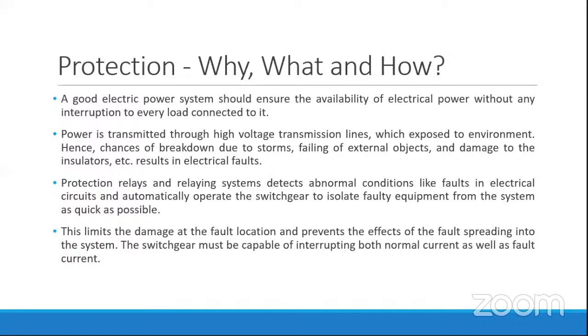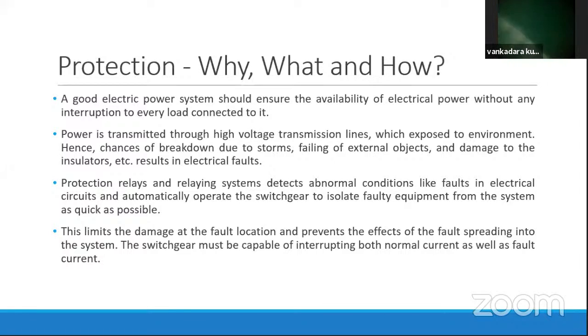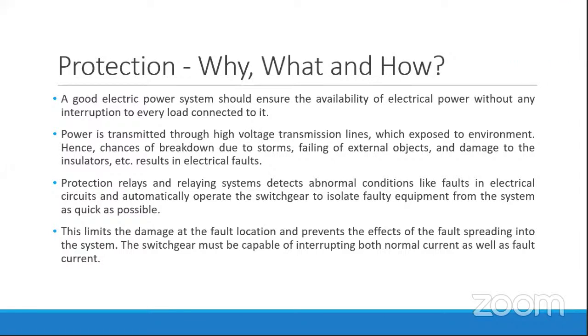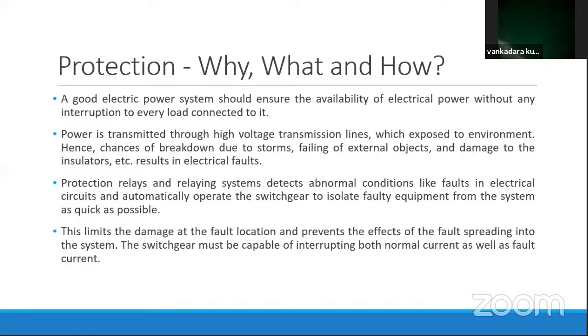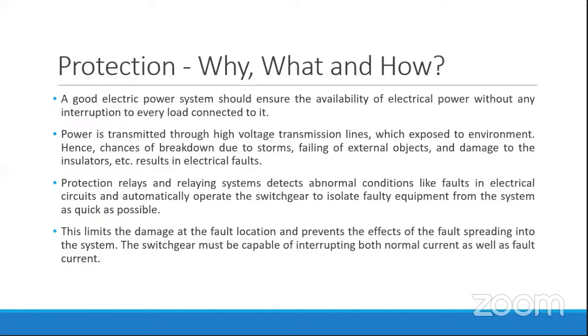A relaying scheme detects abnormal conditions like a fault in the network, and automatically operates and gives the tripping command to the switch gears like circuit breakers to isolate the faulty part from the system as soon as possible, so that the healthy system can be saved. And this will limit the damage at the fault location and prevent the effect of the fault spreading in the system. So the switch gear installed for this must be capable of interrupting the fault, and it should also be able to withstand the normal running load.